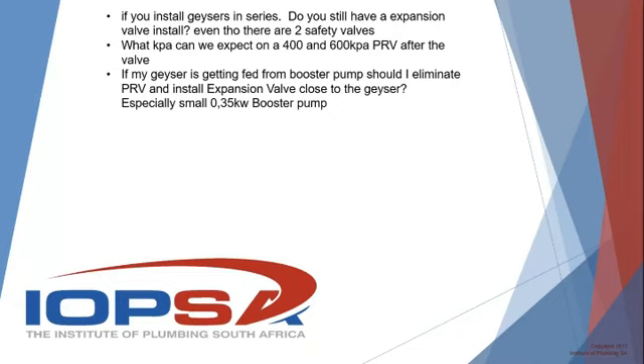If my geyser is being fed from a booster pump, should I eliminate the PRV and install an expansion valve close to the geyser, especially with a small 0.35 kilowatt booster pump? Once again, we go back to what is allowed in the standards. The standard says your closed or unvented geyser shall have a pressure control valve. The only place where you can forego the pressure control valve is if you have a closed geyser installed in a building that was designed and plumbed to supply cold water from a tank system at some point. That must be at a specific height and must not exceed the rating of the geyser, and so on. But that's the only time that you can forego a PRV.